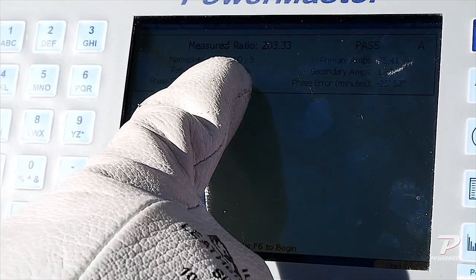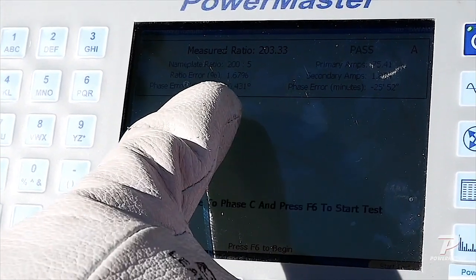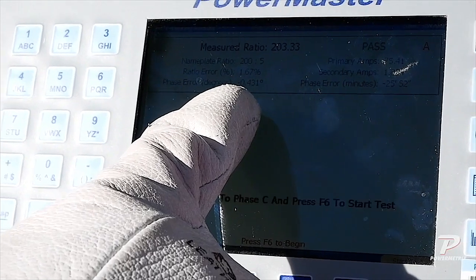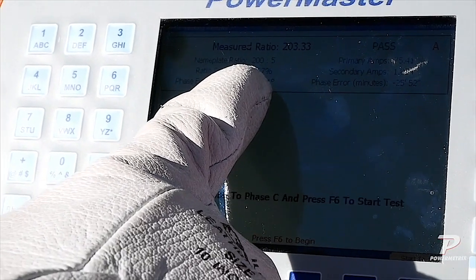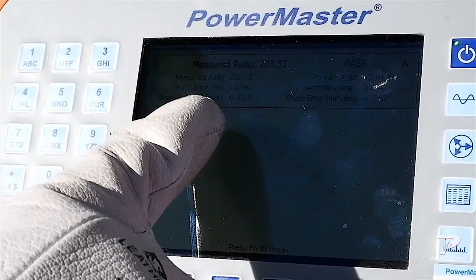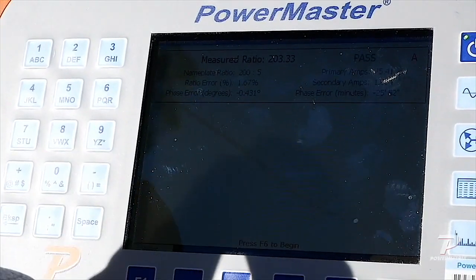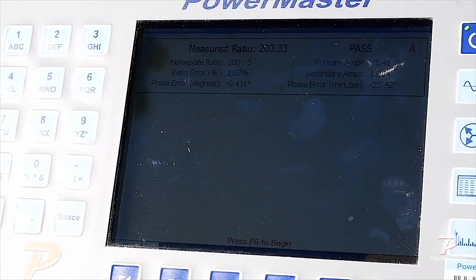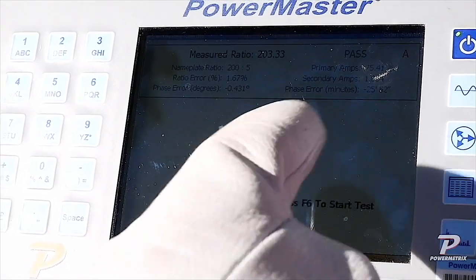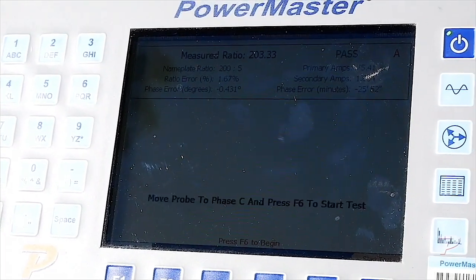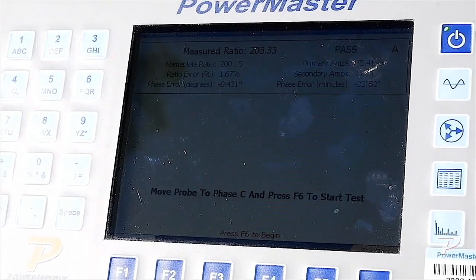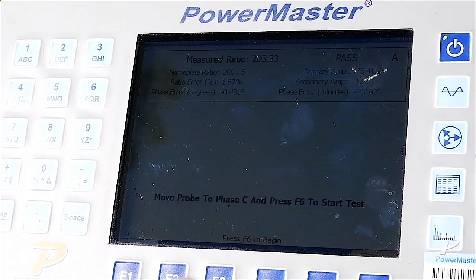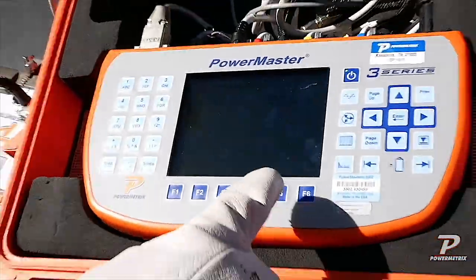Perfect, so we get our pass, and it's showing that's a 200 to 5, which is correct from what we've seen. Our phase angle error isn't giving us any problems, and the ratio is good. If it had been a red fail, we would have followed the red numbers to see where our problem was, whether it was a phase angle error problem or a ratio problem. In this case, both meet our requirements, so we get the green pass versus the red fail, and we love that. Now he's going to move over to C phase and press the button to test it once he gets that high volt probe in position.